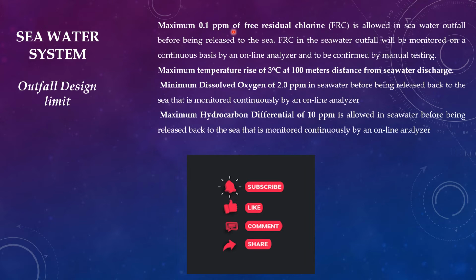FRC should be 0.1 ppm. FRC in the seawater outfall will be monitored on a continuous basis by an online analyzer and confirmed by manual testing also. The maximum temperature rise is 3 degrees centigrade at 100 meters distance from the seawater discharge. That is, if the seawater inlet temperature is X, then the outlet temperature should be X plus 3 maximum, and it is discharged to the sea.